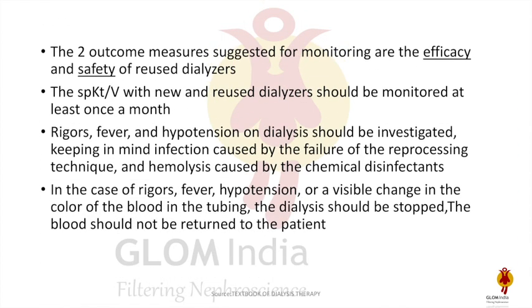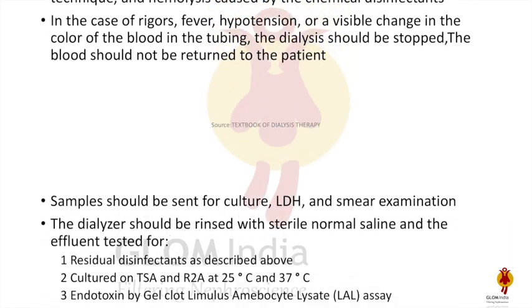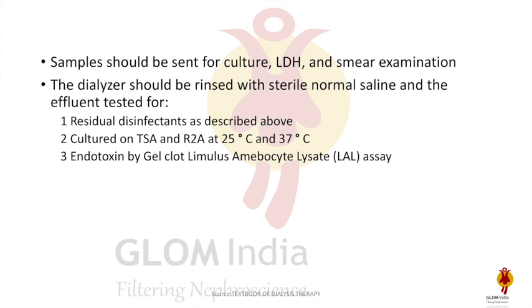For monitoring of outcome and quality control in dialyzer reprocessing, the most important things are efficacy and safety. Efficacy is monitored by KT/V, and safety is related to physical reactions such as rigor, fever, or hypotension. If there is any visible change in the color of blood in the tubing, dialysis should be stopped and blood should not be returned to the patient. Samples should be collected for culture, LDH, and smear examination, and the dialyzer should be rinsed with sterile normal saline and tested for these parameters.